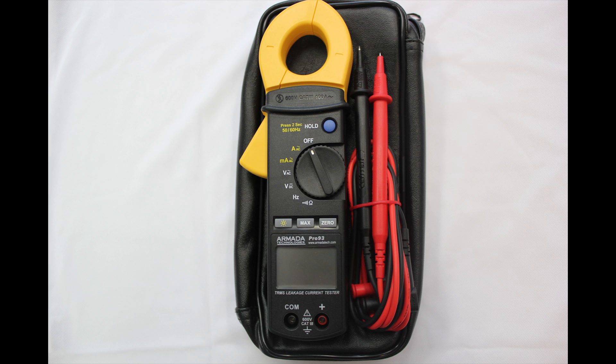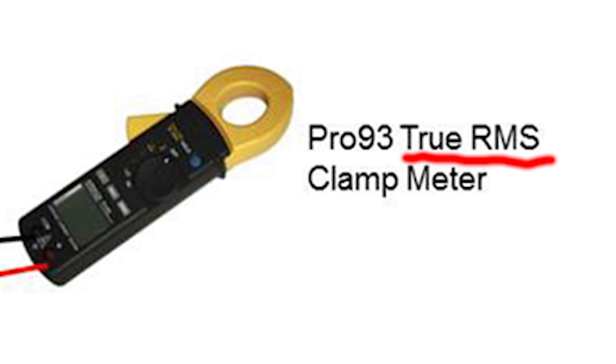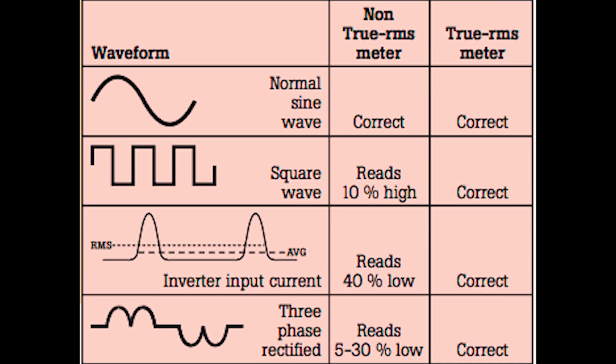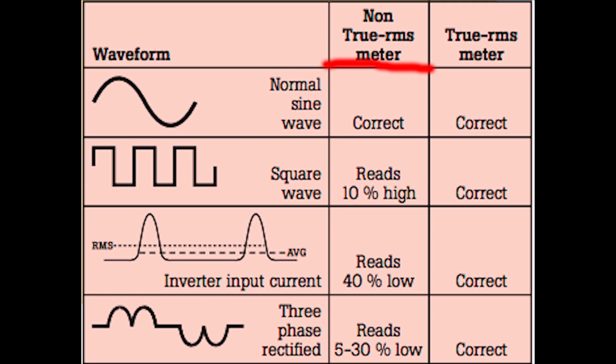In addition, you want to have true RMS capability on your multimeter. True RMS means that the meter is accurate 100% of the time no matter what your AC sine wave looks like—square wave, sine wave, distorted wave, it doesn't make a difference. It's going to be accurate all the time. If you just get an averaging milliamp clamp meter, it may or may not be accurate. It won't be off by tremendous amounts, but you want the most accurate meter you can get, and they're not that much more expensive to get a true RMS version.